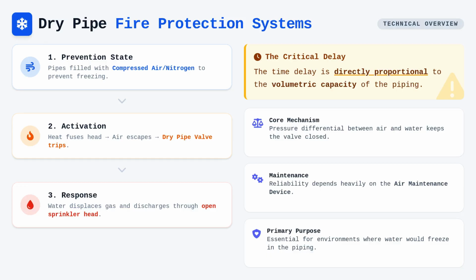The fundamental challenge here lies in the time delay caused by the necessity of exhausting this compressed gas before water can reach the discharging sprinkler. This delay is directly proportional to the volumetric capacity of the system piping and the reliability of the air maintenance device. As a professional, you must understand that the differential between the air pressure and the water supply pressure is the key mechanism keeping the valve closed until the detection of a fire-induced pressure loss.